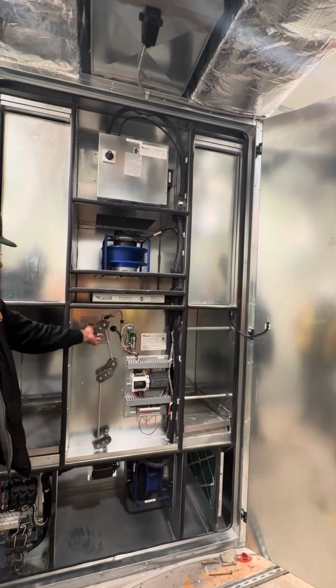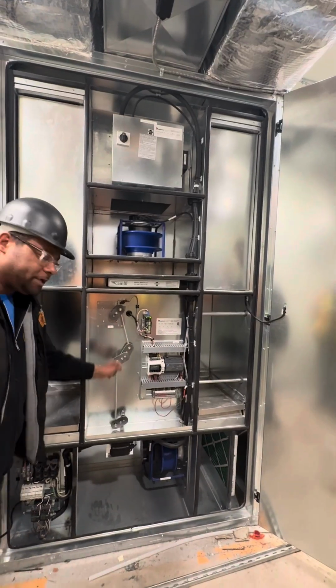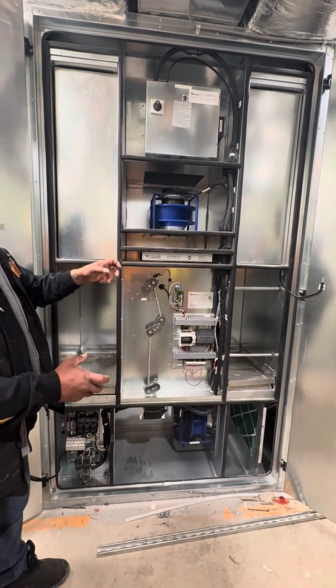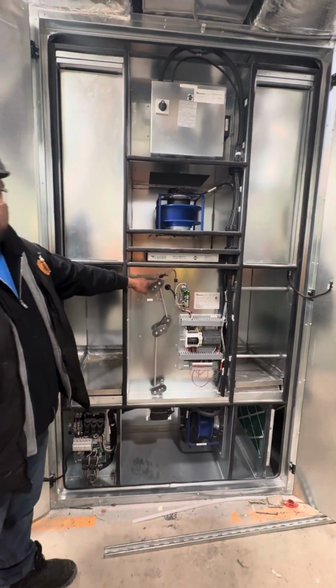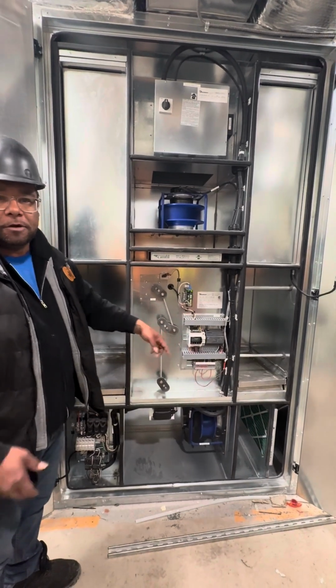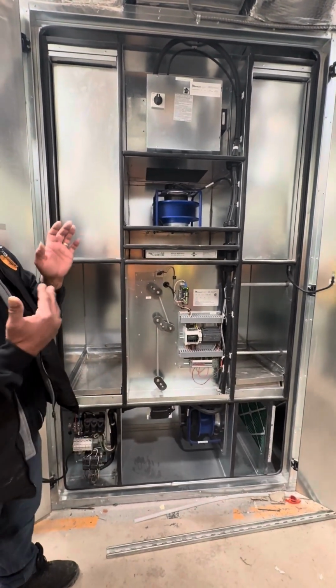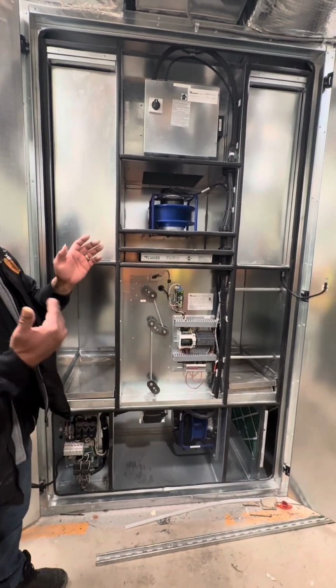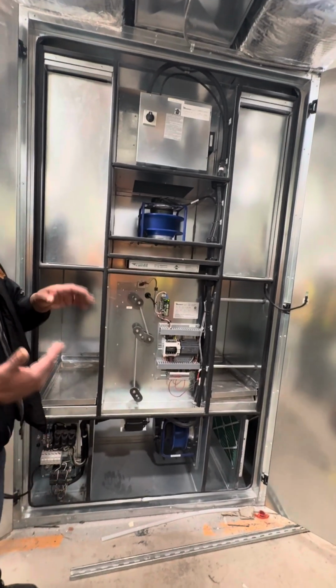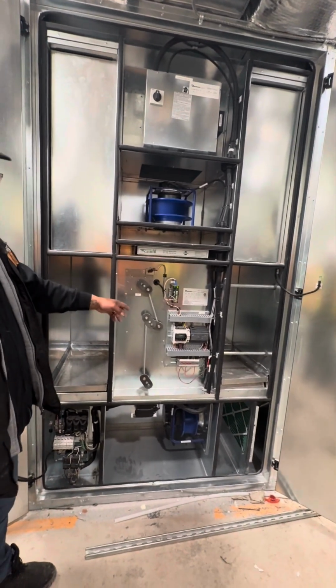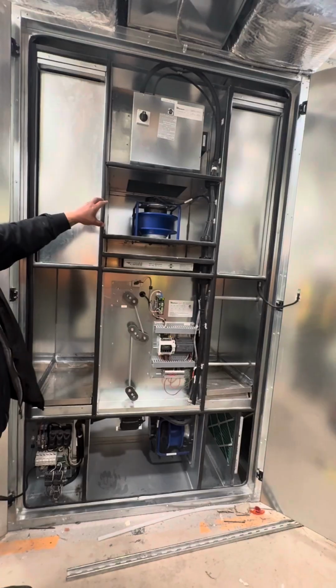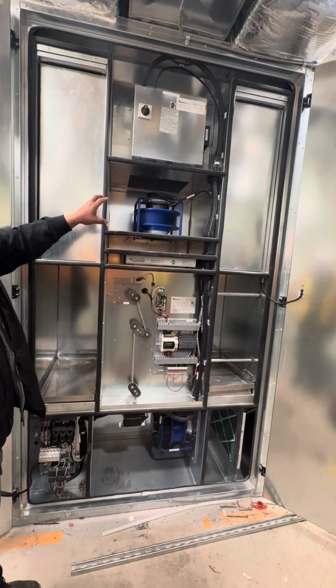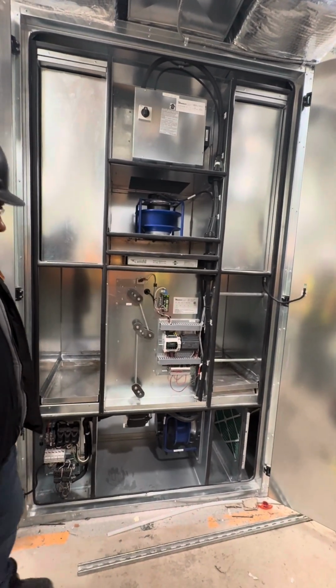And the linkages. Shake the linkages, make sure everything's tight. Again, if the linkage doesn't prove, that switch won't prove, and it'll throw an error code. Those will go back and forth every 30 seconds-ish, back and forth, back and forth. So there's a lot of movement there yearly. Check those linkages, change the filters, check for grease still on there. Need some grease, give it some grease. Put the filters back in.